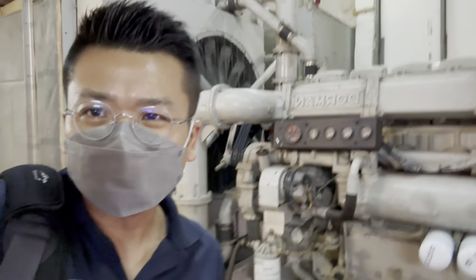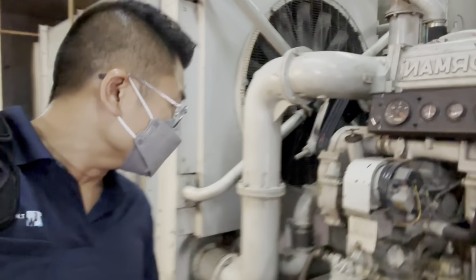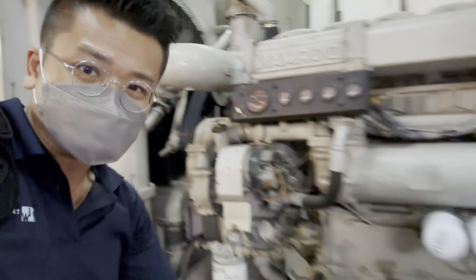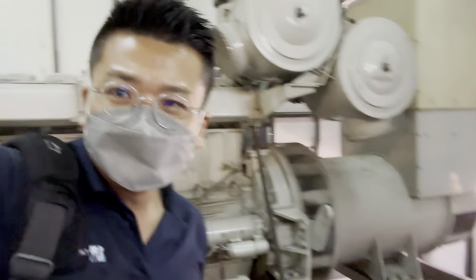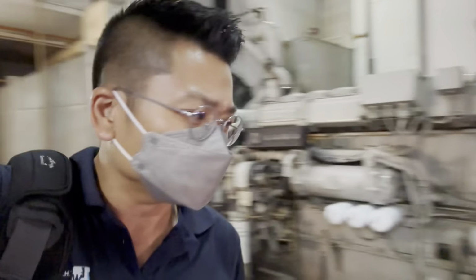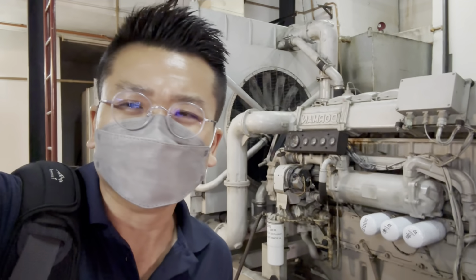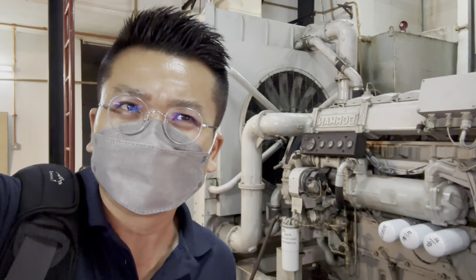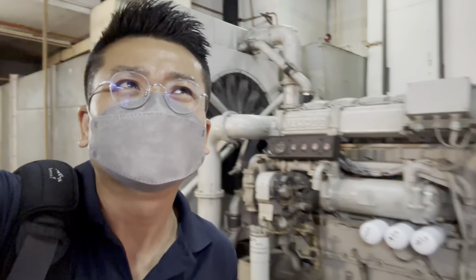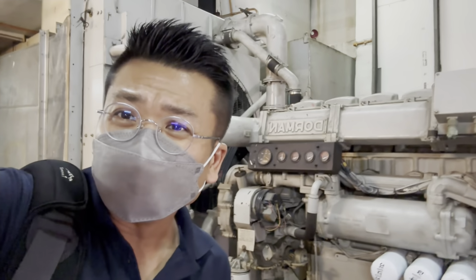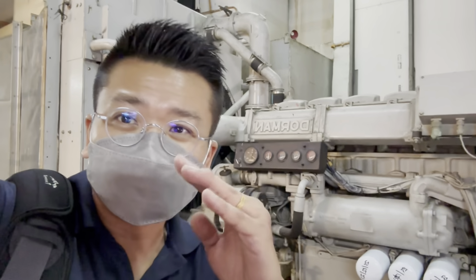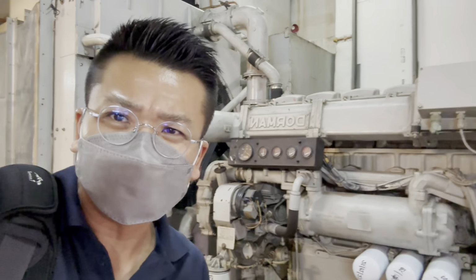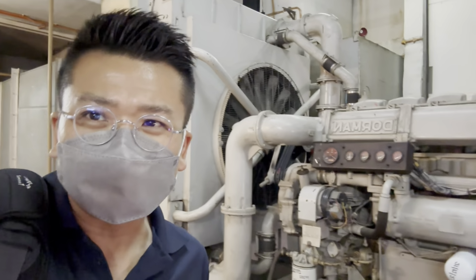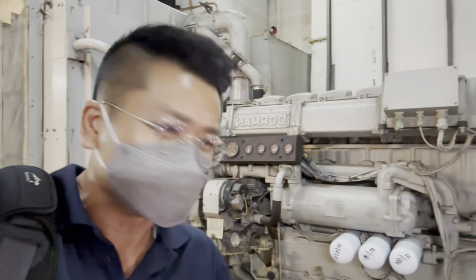It is very important to know that while the genset is in operation, the alternator should be able to charge your battery. This is important because if your battery just drains off during cranking, the voltage will drop from 28 volts, for example, to maybe about 24 or 25 volts. If it doesn't charge, the voltage won't come back to the original position, which is 28.